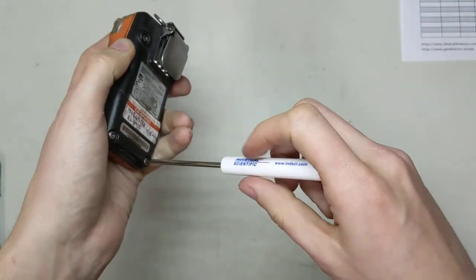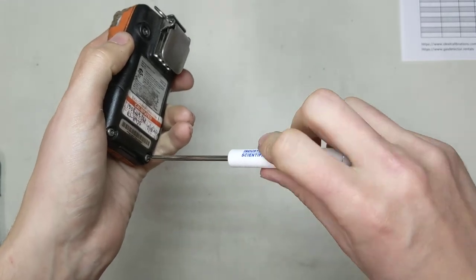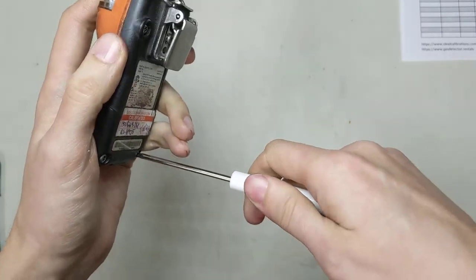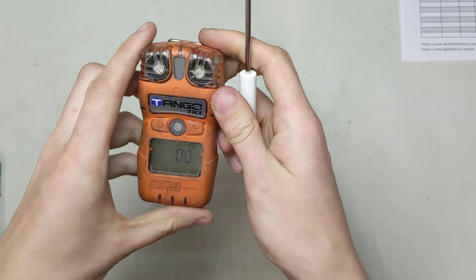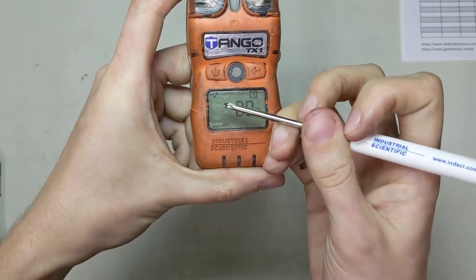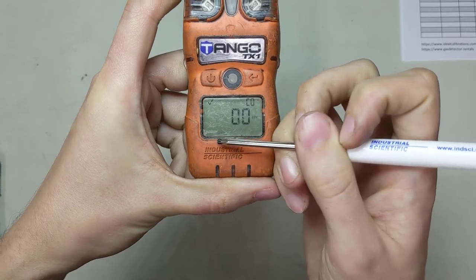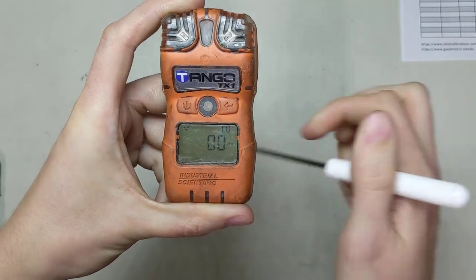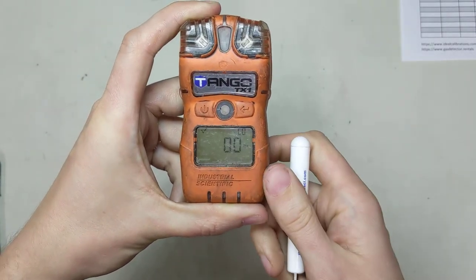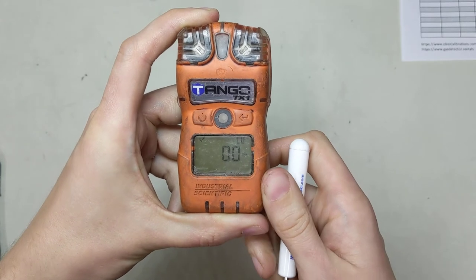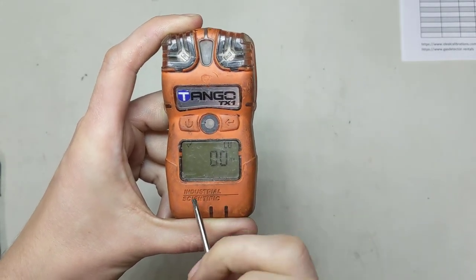That's actually why I like this screwdriver. However, the round design makes it a lot harder to over-press on these screws. Slips a lot easier than you can tell. Okay, good. And you can see now, there's the checkbox here. And there's no error down in here. So this probably fixed the issue we were having. I'm going to put this back on the calibration dock and put it through a cal.